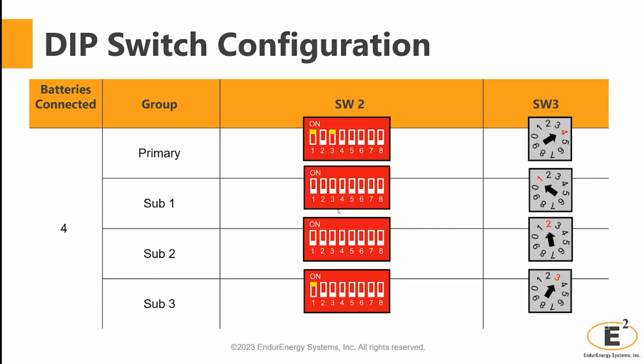In each array of batteries, you will determine one battery that's the primary connection to the inverter. That primary battery will have SW2 and SW3 set up as the image shows. SW2 will have positions 1 and 3 on, and the selector switch will have position 4 selected. So the primary battery will always have the number of batteries in your array set in SW3.